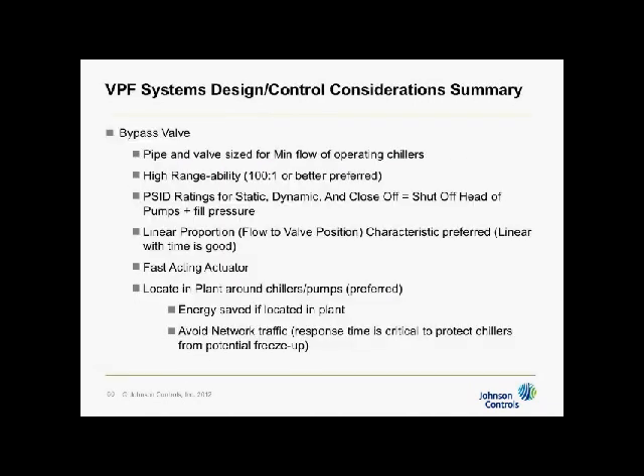Bypass valve, we talked about these things up here. We also want to have a high rangeability for the valve, 100 to 1. Rangeability of a valve is the max flow that the valve can handle, ratioed against the minimum controllable flow that the valve can handle. We need to have PSID ratings for static, dynamic, and close-off equal to shut-off head of the pumps, technically, plus the fill pressure. The static rating is the casing of the valve.